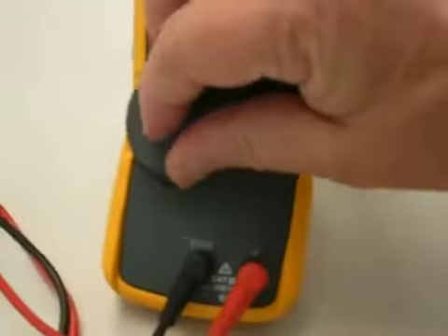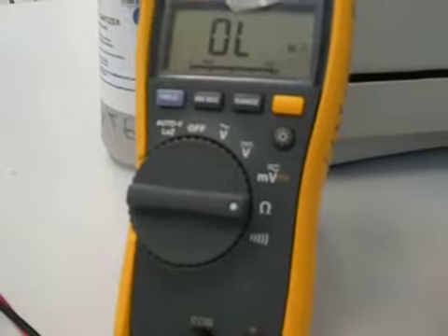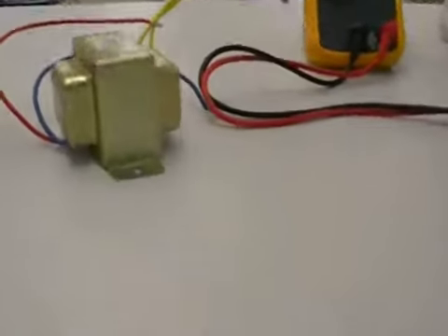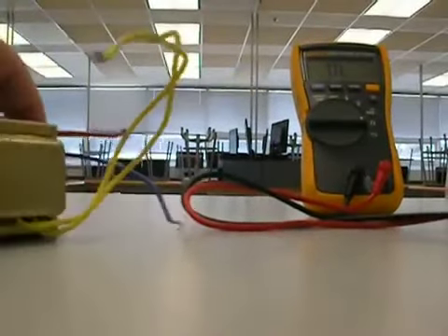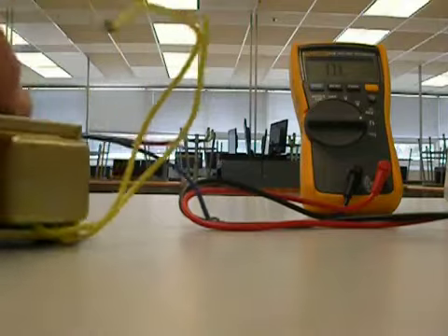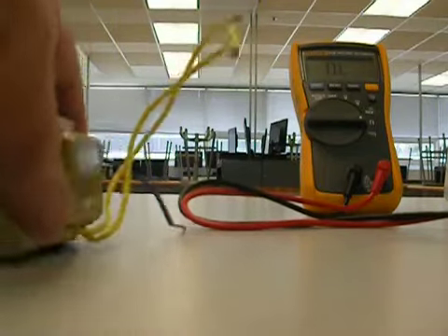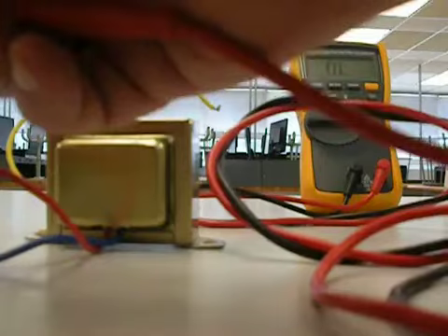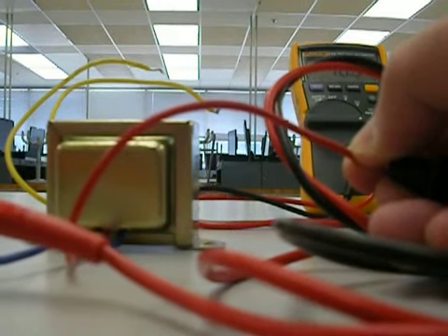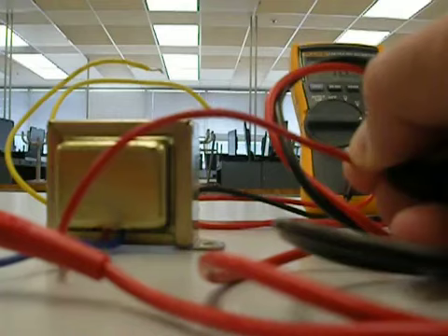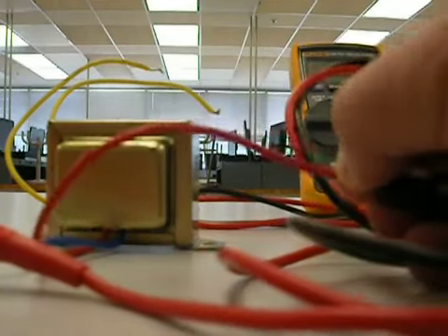So once you have your supplies, let's get started. First thing to do, set the multimeter to resistance. Okay, once you got the meter set to resistance, you're ready to do some tests of that transformer. You got a red and a blue wire and a pair of yellow wires. So one set is the primary, the input wires. One set is the secondary, the output wires. So let me get here between the blue and the red. And I just happen to know that on this particular transformer, this is the primary wires. So this is the input side. And I'm reading around 50 ohms.